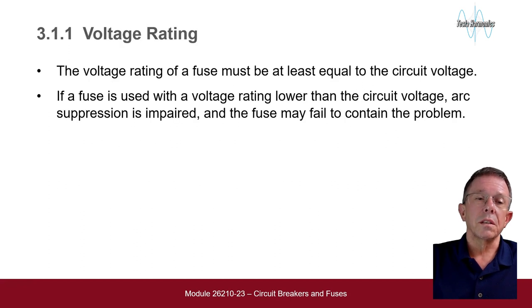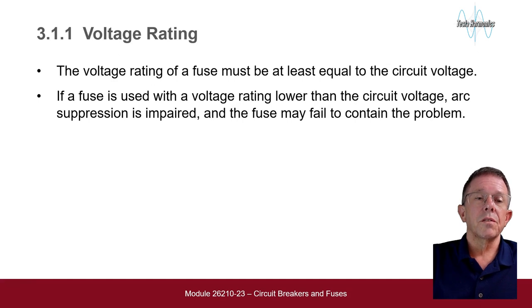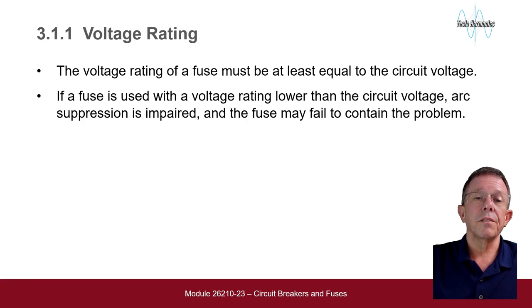Voltage Rating. The voltage rating of a fuse must be at least equal to the circuit voltage. If a fuse is used with a voltage rating lower than the circuit voltage, arc suppression is impaired and the fuse may fail to contain the problem.